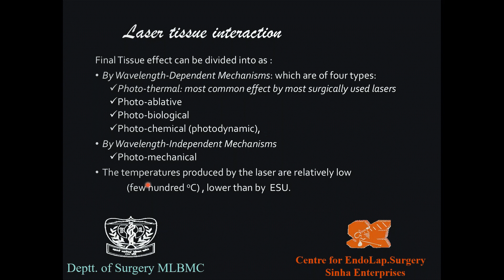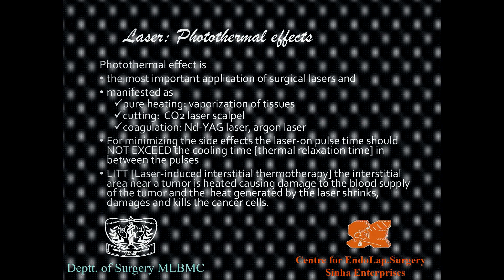The photothermal effect is the most important application of surgical lasers, manifesting as pure heating leading to vaporization of tissues, cutting (as with CO₂ laser), or coagulation (as with Nd:YAG or argon laser). To minimize side effects, the pulse on-time should not exceed the cooling time or thermal relaxation time. If the pulse on-time is longer than the cooling time, harmful heat spread occurs in the surrounding tissue.